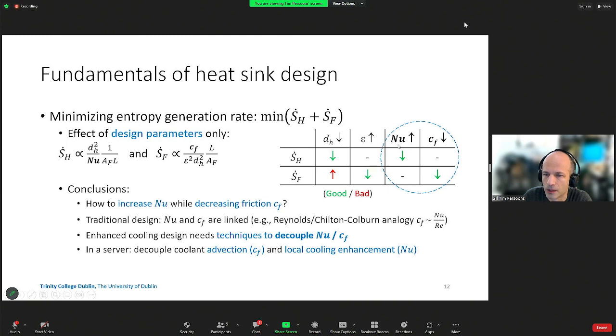But if you look at the effect of Nusselt and the friction factors, obviously we want to increase the Nusselt number because that decreases SH, and we also want to decrease the friction factor, which would decrease SF. But the problem is that, of course, with the well-known Reynolds analogy, these things tend to be coupled. So if you increase heat transfer, you typically also pay a penalty and increase pumping power. So, better designs of heat sinks and of cooling systems for servers, if we bring it back to a server, better designs will try to decouple those two things. So for a server, that means that we want to decouple the advection, the moving of fluid through the system, from the local cooling enhancements. So we want to separate those things out to some extent, so we have more control over the system.